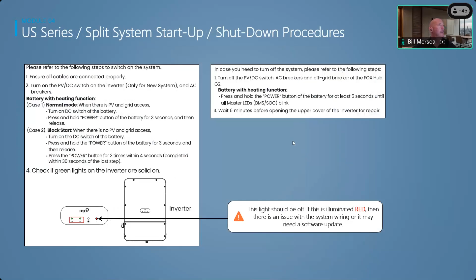In the case where we need to do a black start, it's pretty simple. On both the all-in-one and the split system, when you're turning that DC switch back to the on position, you're going to hold that power button on the battery for 3 seconds, release, and then do that 3 more times within 4 seconds—basically off, on, off, on, off, on. Doing that 3 times tells the system it needs to do a power cycle and turn on, so make sure that you turn on through your solar. Just wanted to give you guys a little information on that.